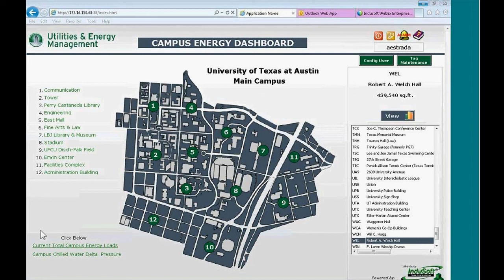The fact that we can go after data in the historian takes the load off of the typical way that trending is done with some of our other automation systems that may access a PLC directly for data, and then we have to set up another database to log that data. That's really something that we wanted to go away from.